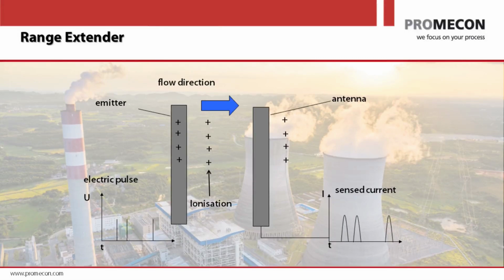The range extender is basically another rod that is installed upstream of our airflow measurement. And this range extender generates electric pulses that ionize the air with a small corona discharge. If you have this range extender in the gas, what you will see is that you have ionized air clouds then coming from the range extender. Why are these ionized air clouds important? Because they induce an electric current on our antennas, like the dust, same thing.